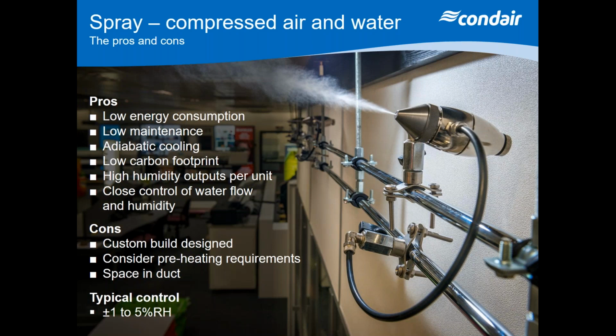So if you've got a very tight area, you may need more nozzles with a smaller air cap to give you the smaller duties to get your capacities in. In terms of the operation, we're trying to regulate the flow of air pressure into these units with a panel, which is going to have a regulator for air and water coming in at 4 bar, and then reducing that down to 2.2 bar for the air, and obviously whatever the capacity of the nozzle is on the water side. Once we get that correct and the design of the pipework is correct, then we can spray uniformly across the room.